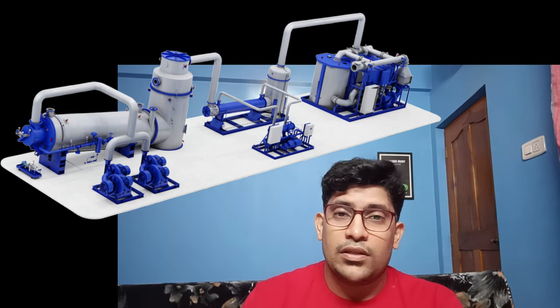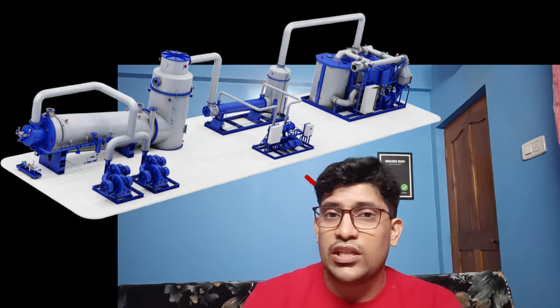In IGG we have four components: the burner, the cooler, the chiller, and the dryer. I have referred to the Alfa Laval website for today's video. For certain cargo, we need a dew point of at least minus 45°C, up to minus 65°C or lower, and oxygen levels of around 0.5%. Maintaining these levels can be very difficult.